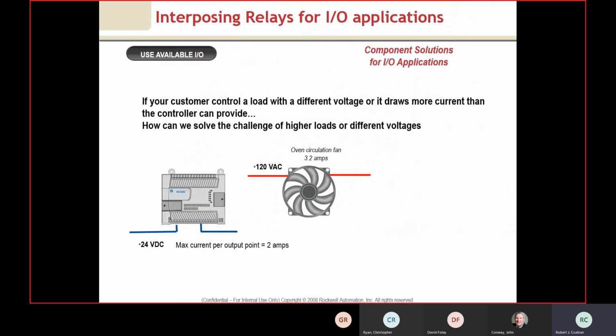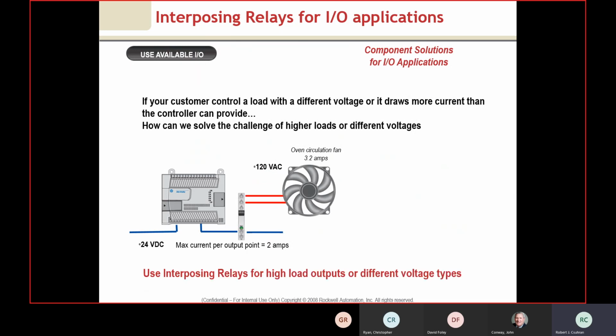Interposing relays, we use these every day. Obviously, the advantage to them is they allow us to provide a differentiating current and power to our load. What we wanted to highlight here is that we're utilizing an interposing relay that would sit on the DIN rail inside the cabinet.